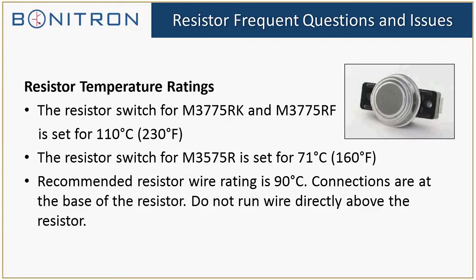The other question about resistors is actual temperatures. Resistors do burn off all this energy as heat, and so we do include a temperature switch with our M3775RK and M3775RF resistors, and for those two, those are set for 110 degrees Celsius, and basically it's just a status. Once it gets up to 110, the resistor will open, and the customer can use that open signal to either shut down their drive or just scale back their process if they need it, or just even have a warning light. But the resistor will continue to function up until the point where it just gets too hot and it just basically melts down. The temperature sensor is really just a contactor.